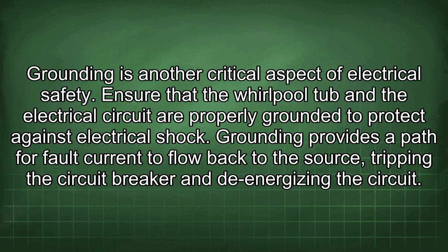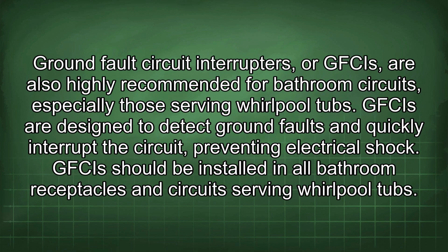Grounding is another critical aspect of electrical safety. Ensure that the whirlpool tub and the electrical circuit are properly grounded to protect against electrical shock. Grounding provides a path for fault current to flow back to the source, tripping the circuit breaker and de-energizing the circuit. Ground fault circuit interrupters, or GFCIs, are also highly recommended for bathroom circuits, especially those serving whirlpool tubs. GFCIs are designed to detect ground faults and quickly interrupt the circuit, preventing electrical shock. GFCIs should be installed in all bathroom receptacles and circuits serving whirlpool tubs.